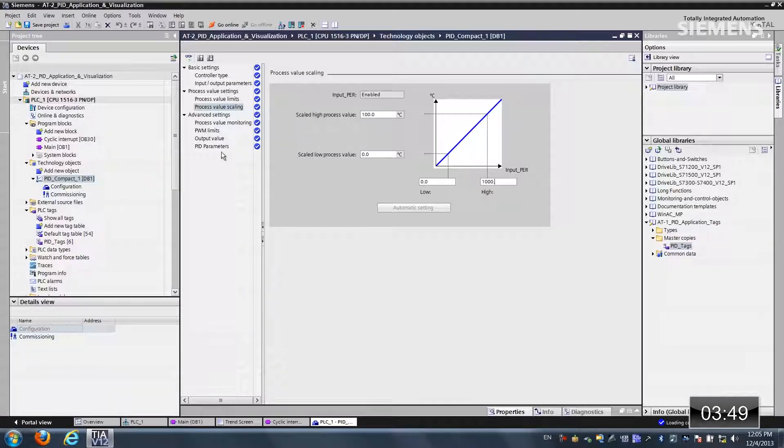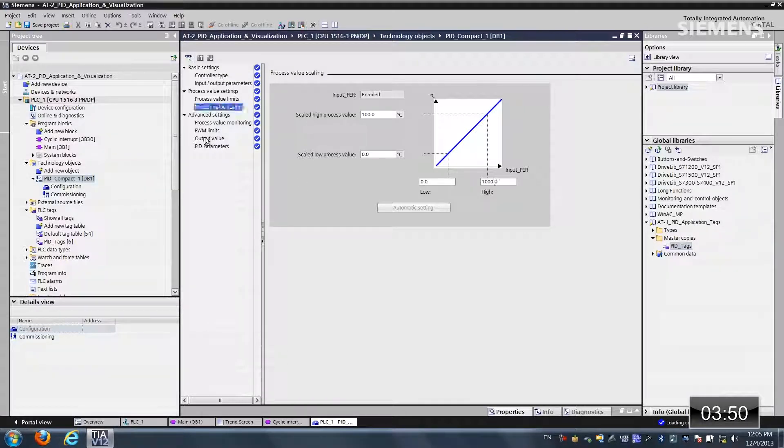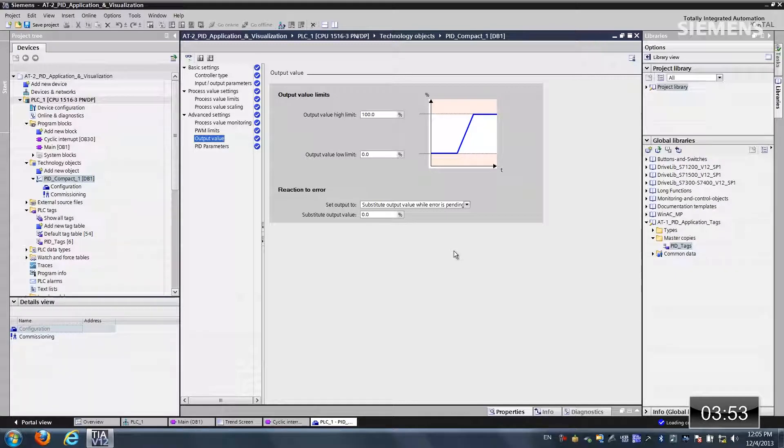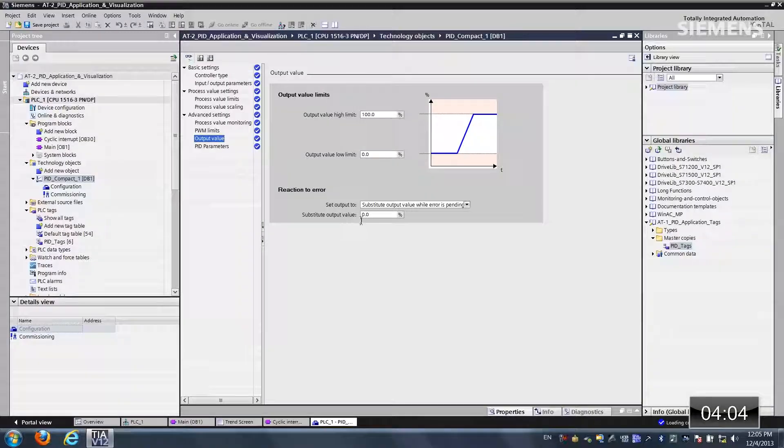And last but not least, on the output value, we also have something reaction to error for this new version 2 PID compact. We can do a substitute value or whatever the last known value is. That way if there is an error, it just maintains steady operation mode. Alright, so now we've done everything.